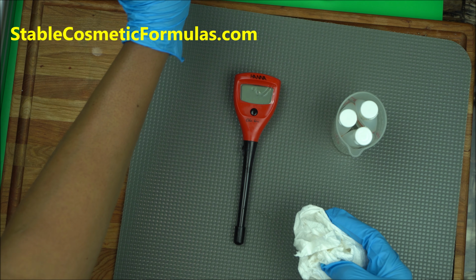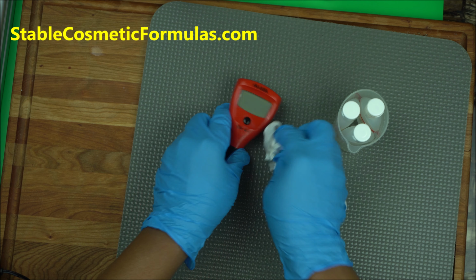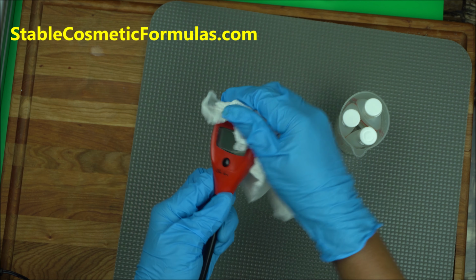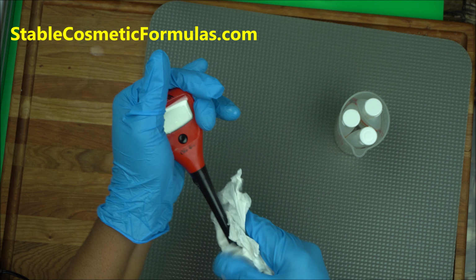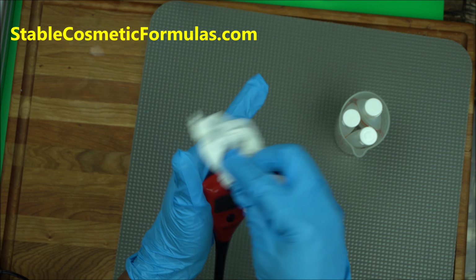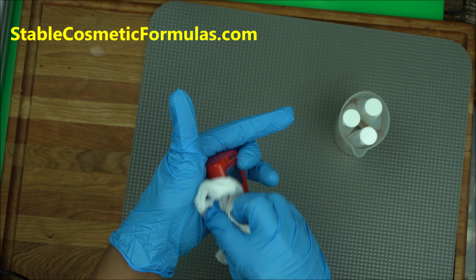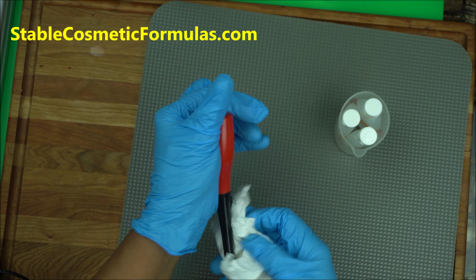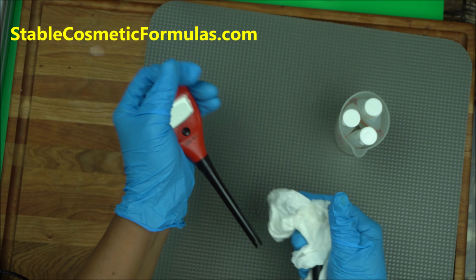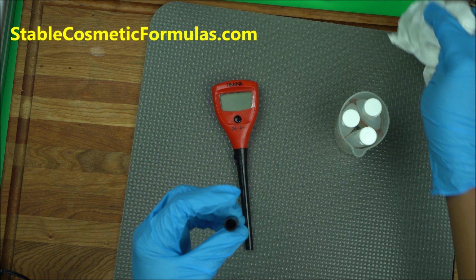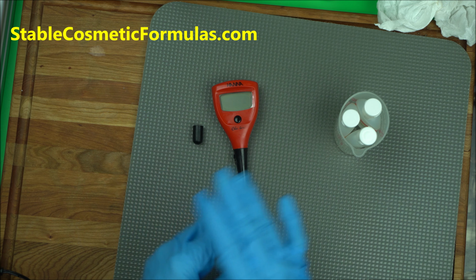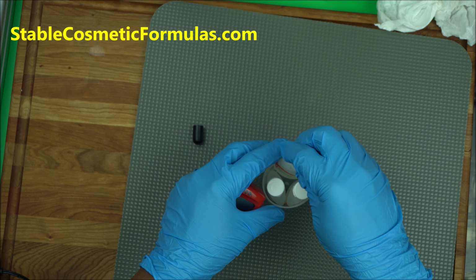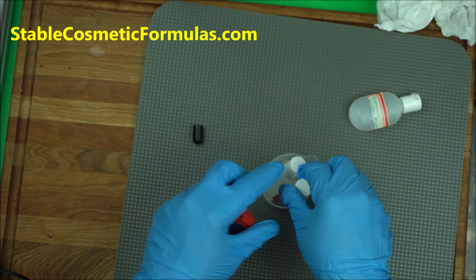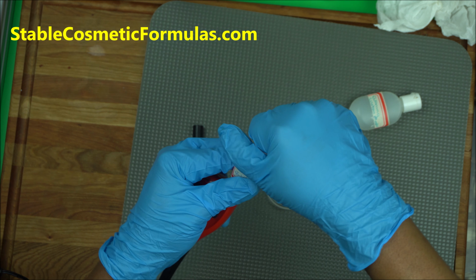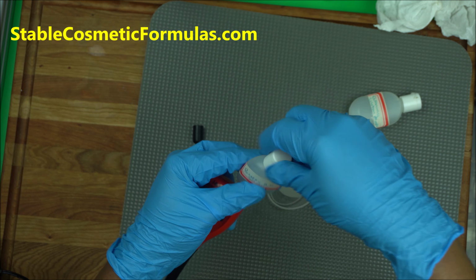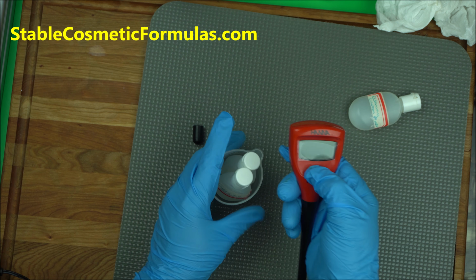You want to make sure what you get is an accurate reading. And don't forget, you always have to have your isopropyl alcohol around you to wipe off. The exception to this is your scale. Do not use isopropyl alcohol to wipe your scale, or you can use it to wipe the outer part of your calibration tool, depending on the brand of tool you have. So we're going to remove that. Then I'm going to go to, this is a cleaning tool, because I'm doing small amounts, so that's why I have all this. I'm going to turn on my HANNA pH meter.